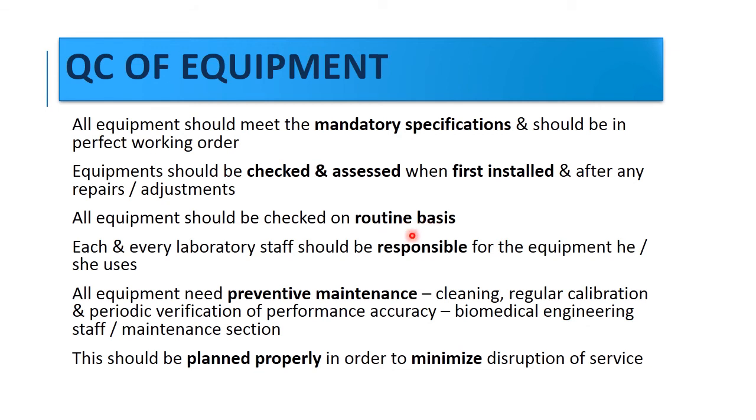There should be a regular check over the equipment. Each and every laboratory staff member should also be responsible when working with the equipment: how to handle it, when to handle it, and all the required measures should be followed by the staff working with the respective equipment. All equipment needs preventive maintenance, so regular maintenance with respect to cleaning, calibration and verification has to be done regularly. These regular checks should also be planned properly so that they minimize the disruption of the service.